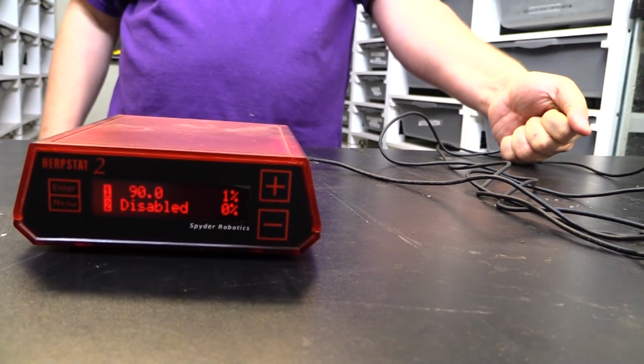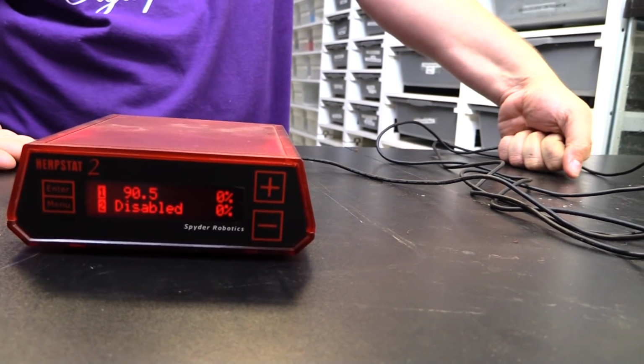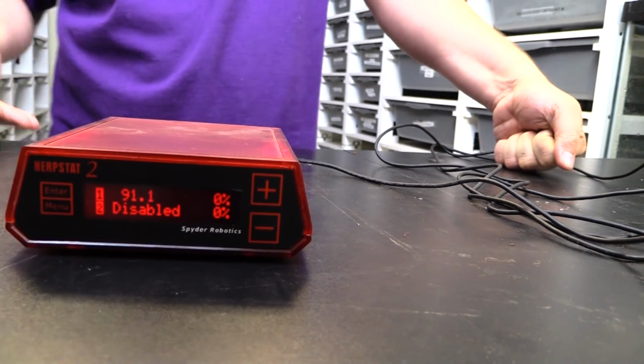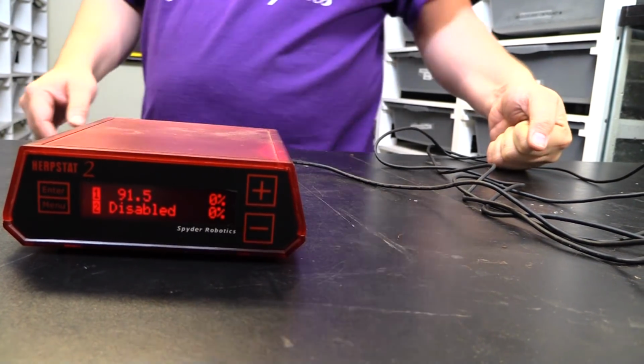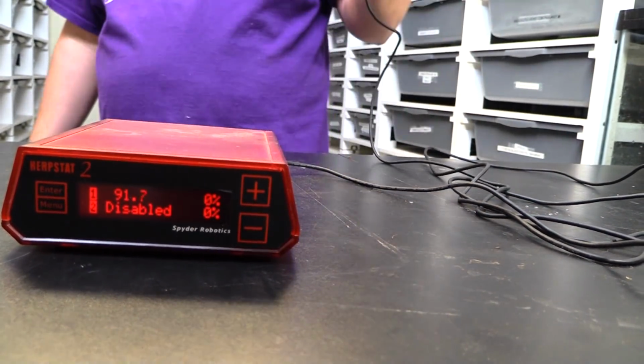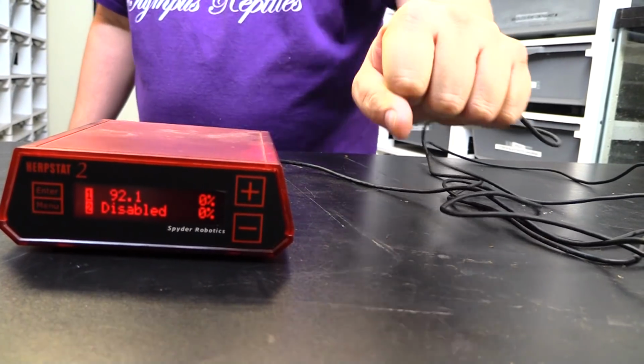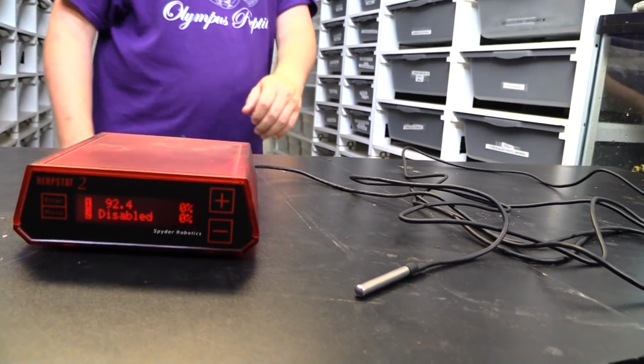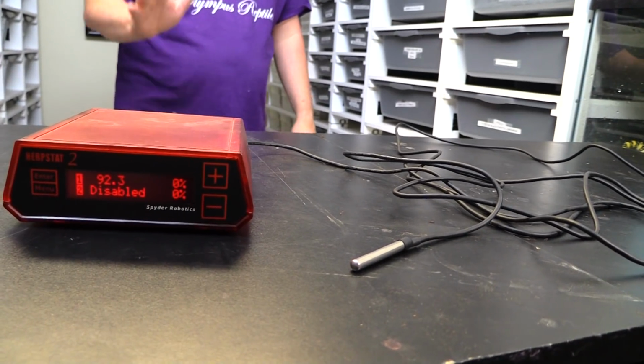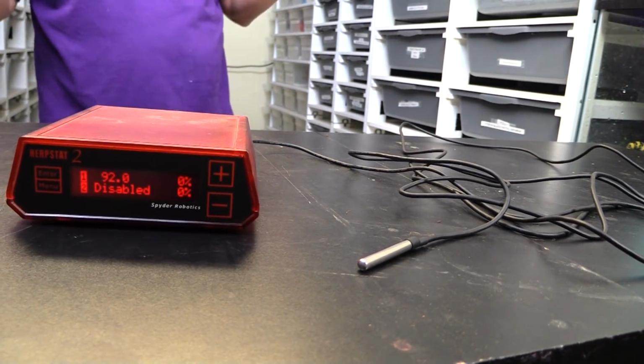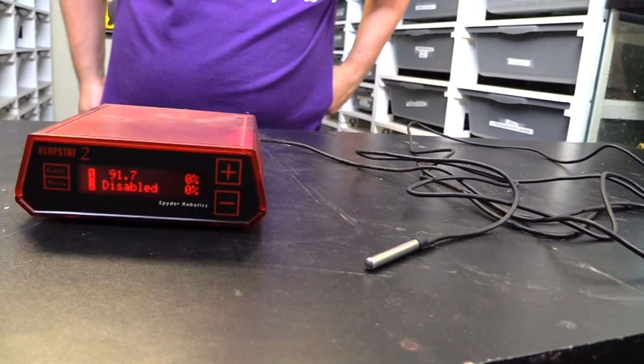89. Okay, so temperature 90, or 89 power? It's at 0 power at 91 degrees. So now it's got to 91 degrees and it says 0 power. The reason it's reading that is because it's in my hand. If I were to drop that probe and let it start to cool off, you're going to see it get below 90, and you're going to see that power start to ramp up. That's how that would dial in.